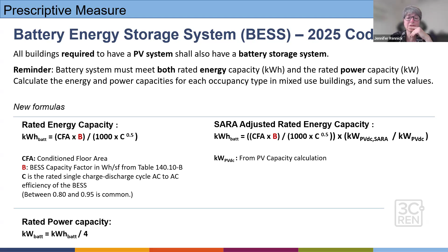They also gave folks, for their battery size, what's called a SARA adjusted rated energy capacity. So if you're taking that SARA alternative for the PVs, then when calculating your battery, you'll use this other formula with a ratio of the kilowatt PV size for SARA divided by the value without SARA. You can also get help from your code coaches and electrical engineers on this, but I put it in here for your reference.